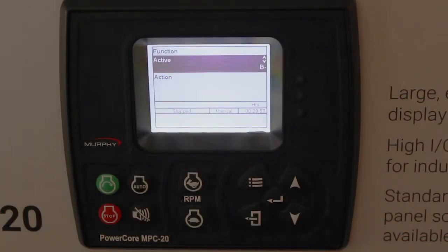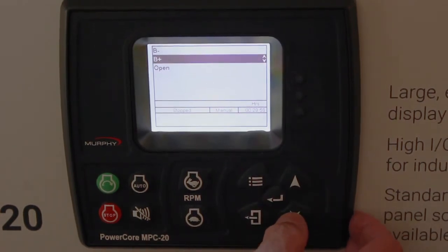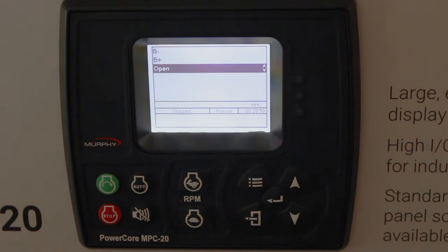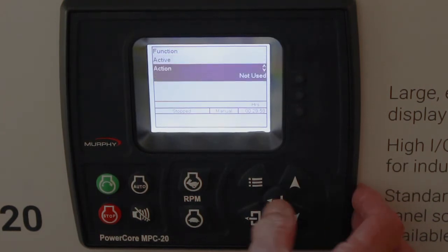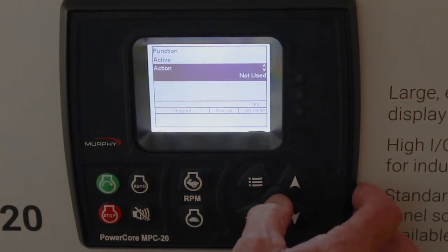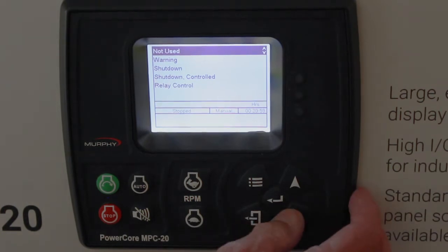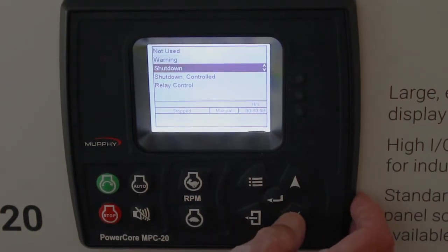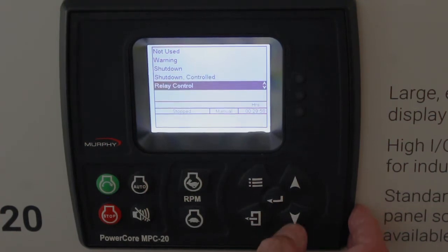Active is active on a ground or B minus. You can change that to be active on B plus, or change it so a contact opens when you have the fuel leak. For the action on a digital input: if it's not a shutdown, it would be not used — like for the float start/stop. You can have it be a warning, a shutdown, a controlled shutdown (which is similar to an auto stop), or you can turn a relay output on with it.